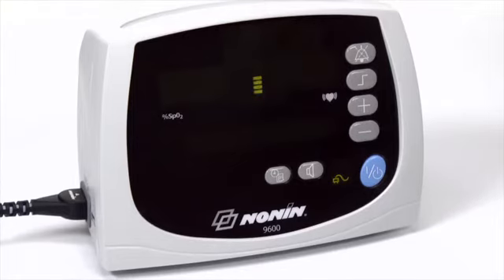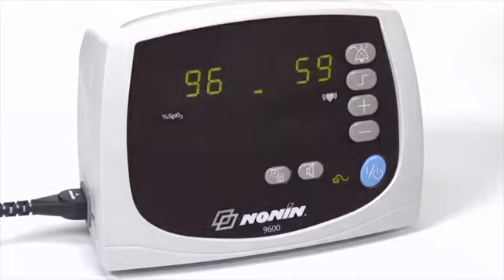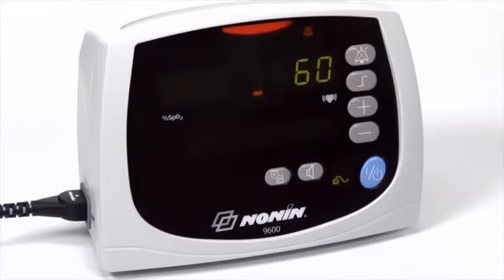When the alarms are in the unlocked setting, the alarm will stop and return to normal monitoring function when oxygen saturation level or pulse rate return to the preset range. This option is controlled by dip switch 3. In the locked alarm position, you must press the alarm silence button to clear the alarm status. Other alarms from the oximeter diagnostics may occur. This will typically generate an error code on the display. You can silence the audible alarm with the alarm silence button.